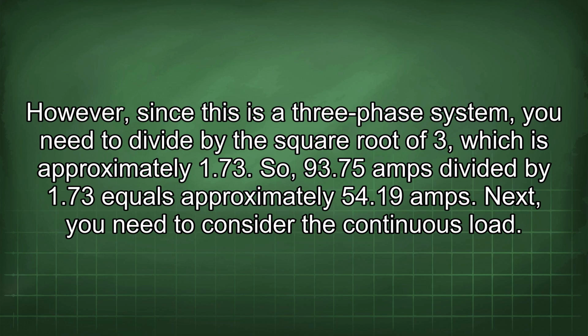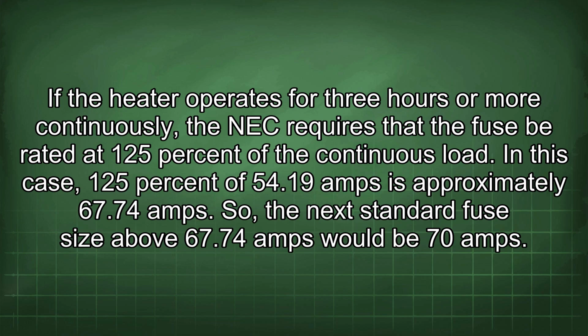Next, you need to consider the continuous load. If the heater operates for 3 hours or more continuously, the NEC requires that the fuse be rated at 125% of the continuous load. In this case, 125% of 54.19 amps is approximately 67.74 amps. So, the next standard fuse size above 67.74 amps would be 70 amps.